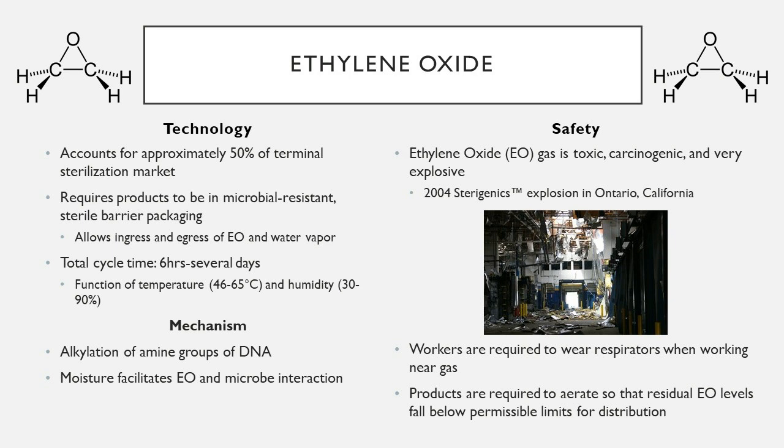Because of these safety precautions, workers are required to wear respirators when working with or near the gas, and products even have to be aerated after they're treated so that residual ethylene oxide levels fall below acceptable limits. In fact, biocompatibility tests are done after sterilization methods in part to look for the toxicity of residual ethylene oxide amounts.